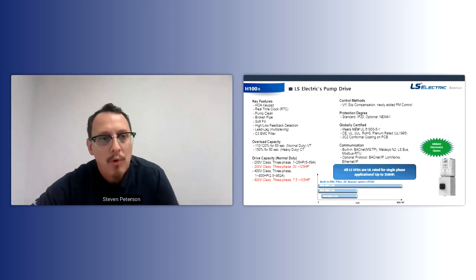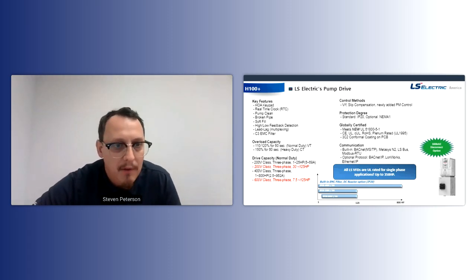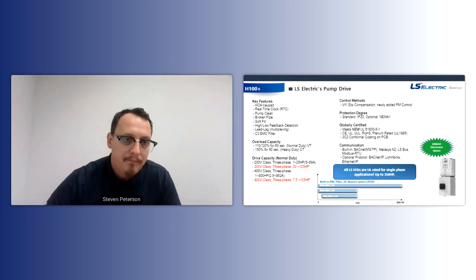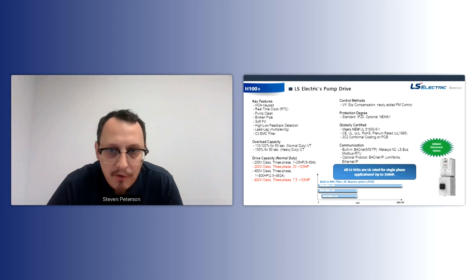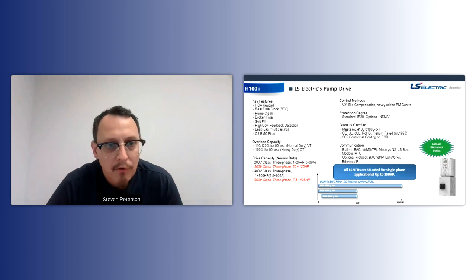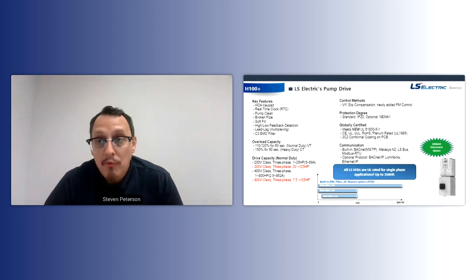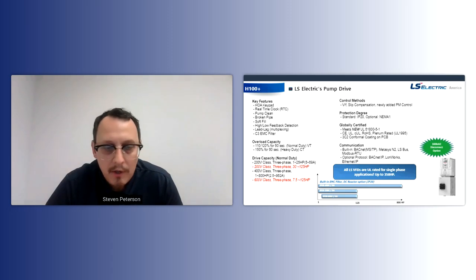As far as hardware, the H100 Plus does have a built-in EMC filter on the 400 volt series drives. That's a C3 EMC filter, for electromagnetic noise that the VFD may generate. I think you'll find most of this is just industry standard as far as capacity. The H100 Plus is a dual rated drive, so you could run it normal duty or heavy duty, variable torque or constant torque. And if you haven't heard those terms before, it's an overload capacity of the drive.